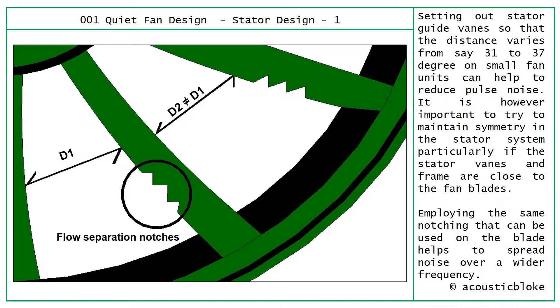Coming back to stator design: applying the same principles used on blades to the stators helps control noise from these elements. Setting stator vane angles so that the distance varies — for example, from 31 to 37 degrees on a small fan unit — helps reduce noise impulses, as the regularity of stator blade positioning can create a pulsing noise as blades pass. It is important to maintain symmetry in the stator system, particularly when stator vanes are close to the blade. The same notching used on blades can be employed on stators to spread noise over a wider frequency.